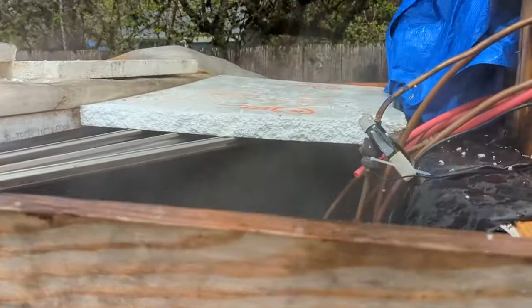Using a 25-gallon per minute pump, we can heat the tank at half capacity, in this case approximately 320 gallons, to 140 degrees in about 2 hours.